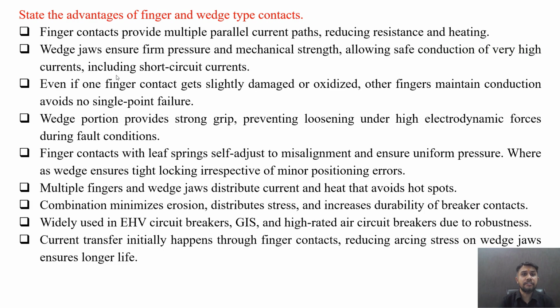The advantages of finger and wedge type contact. So there are several advantages of this type of contact. Some are listed over here. Finger contacts provide multiple parallel current paths, so reducing the resistance and heating. Wedge jaws ensure firm pressure and mechanical strength, allowing safe conduction of very high currents, including short circuit currents.